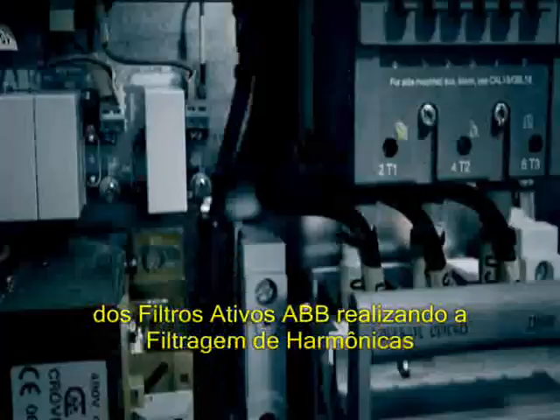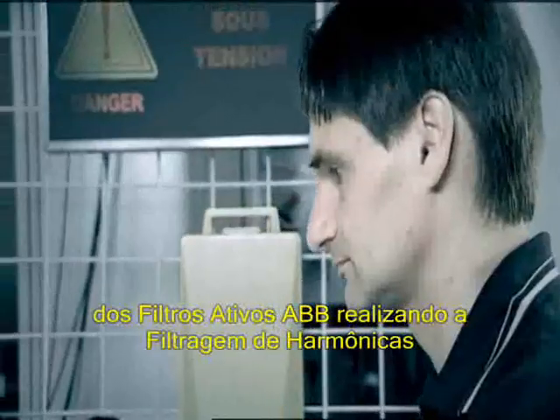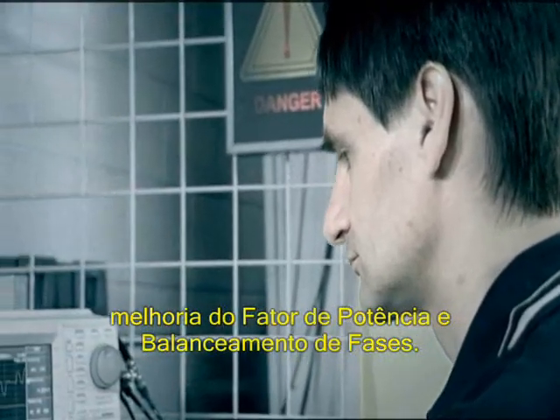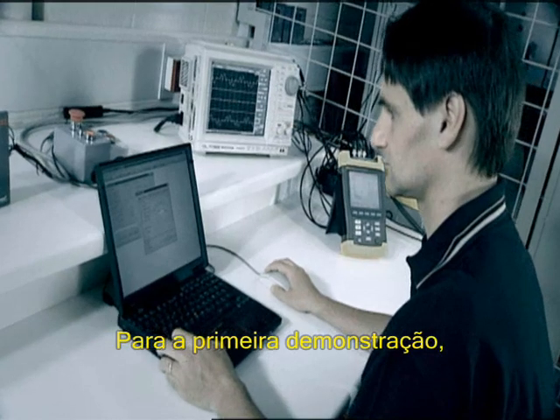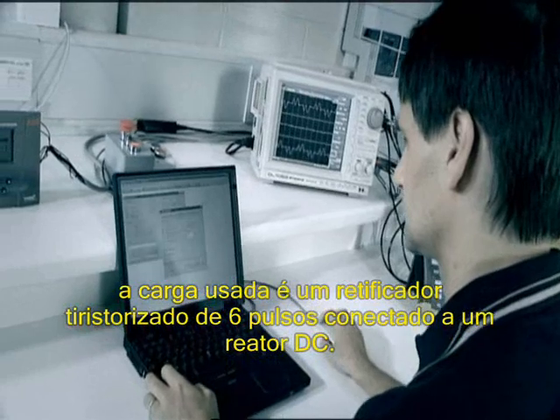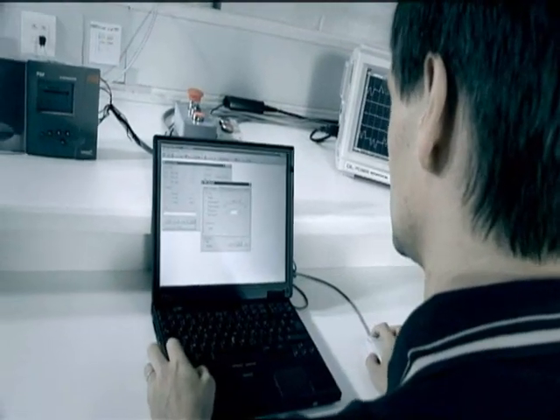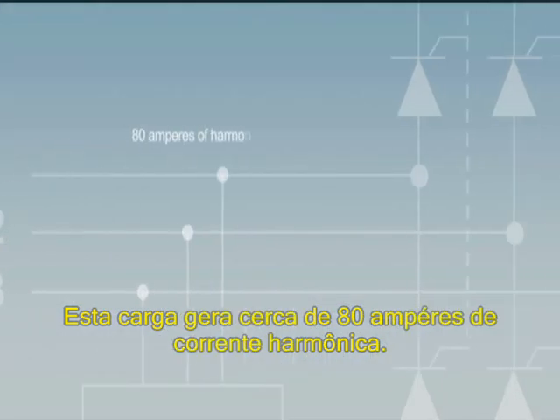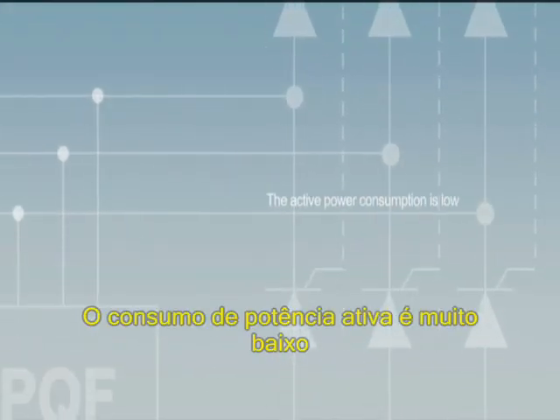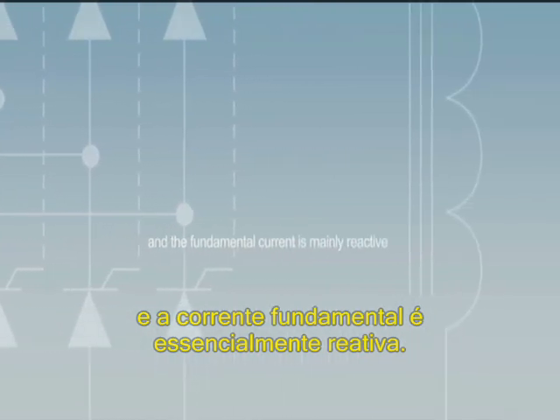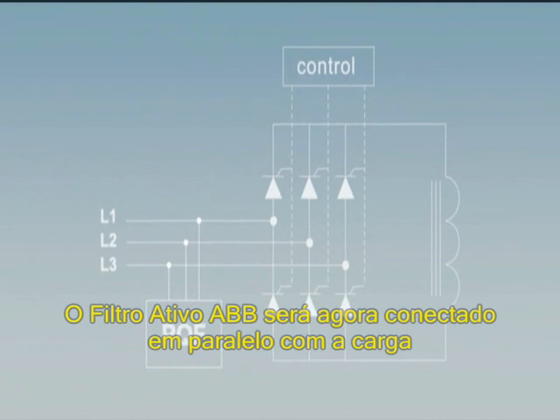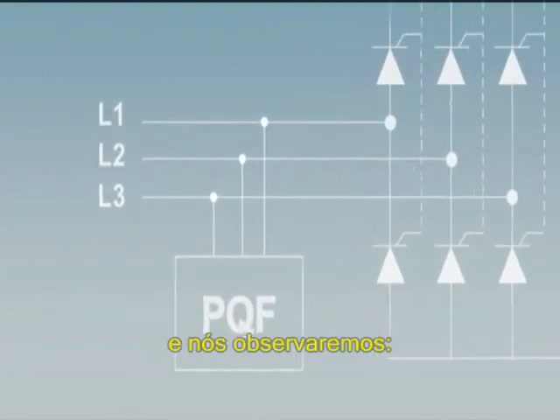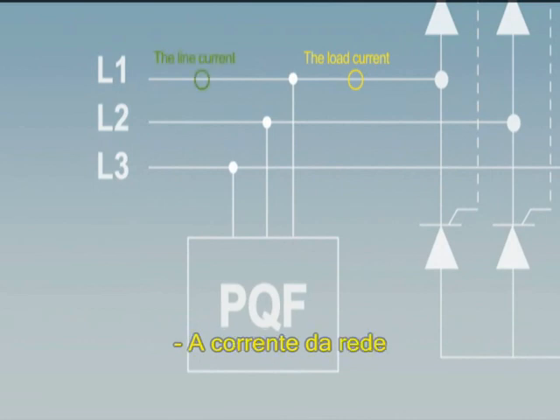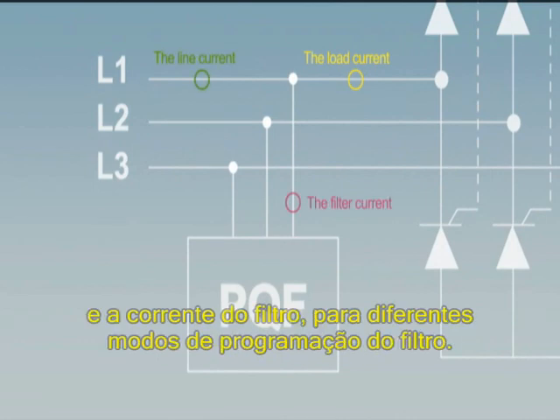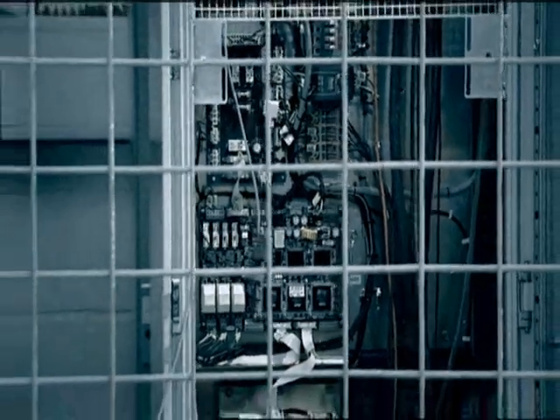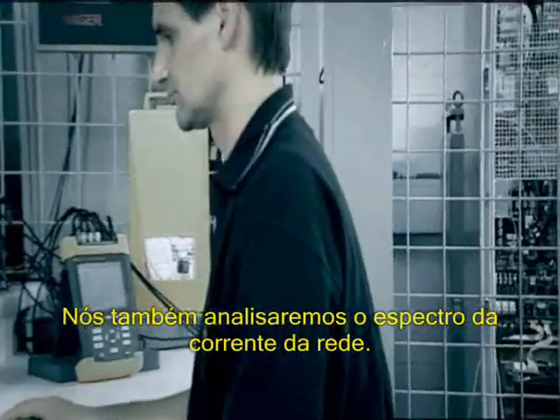You'll now see a real demonstration of the ABB active filters performing harmonic filtering, power factor improvement, and load balancing. For the first demonstration, the load used is a 6-pulse thyristor rectifier connected to a DC reactor. This load generates about 80 amperes of harmonic current. The active power consumption is low and the fundamental current is mainly reactive. The PQF active filter will now be connected in parallel with the load, and we'll observe the load current, the line current, and the filter current for different programming modes of the filter. We will also analyze the line current spectrum.